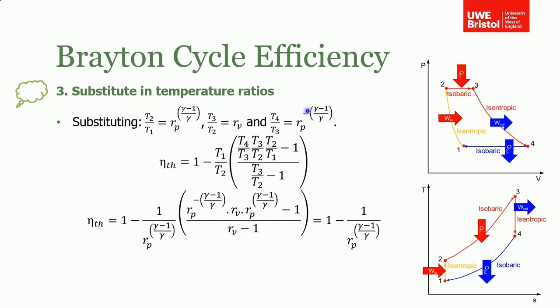Substituting all the temperature ratios into our thermal efficiency expression, we find that the (rv - 1) terms cancel top and bottom, and we're left with the final expression: thermal efficiency equals one minus one over rp^((γ-1)/γ). Gamma is a fixed property of air, so the only variable we can change in our gas turbine is the pressure ratio rp. As we increase the pressure ratio, this term gets smaller and thermal efficiency increases.